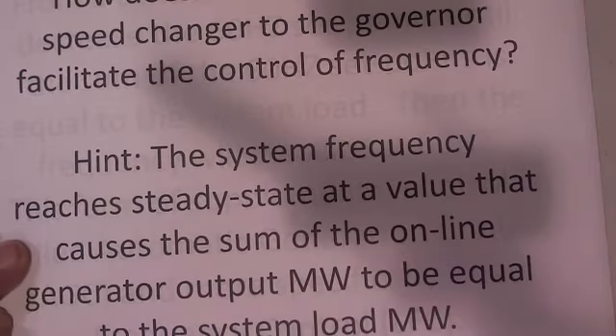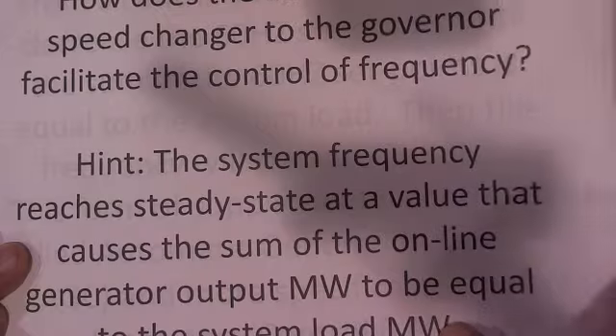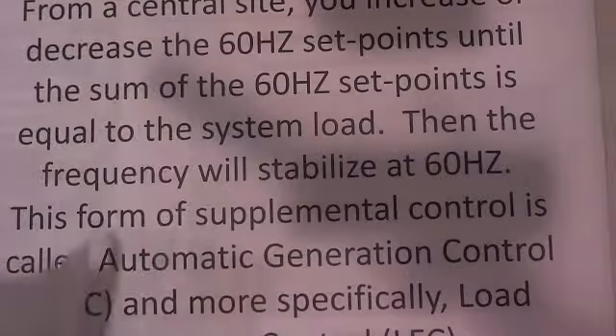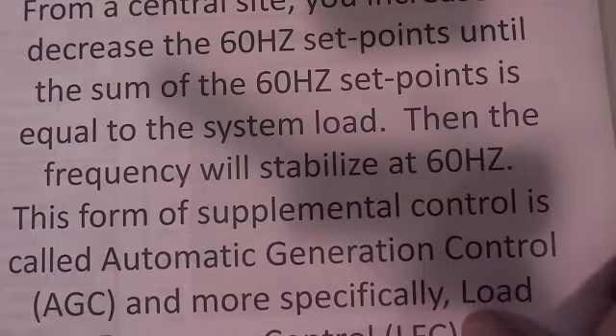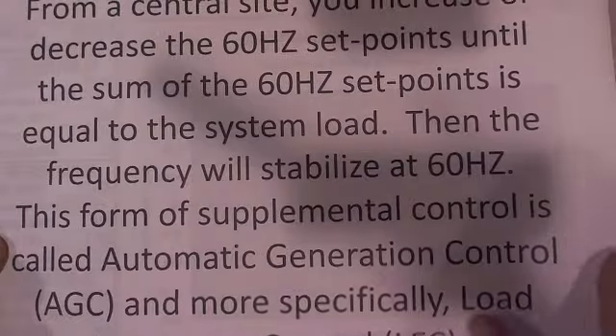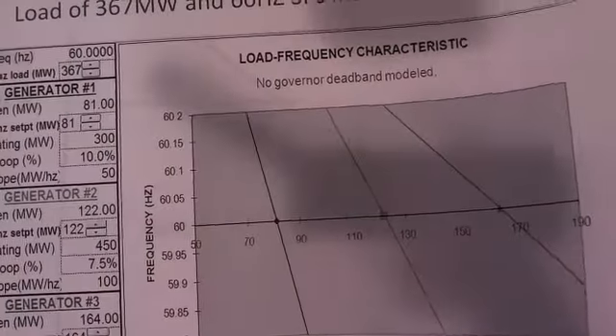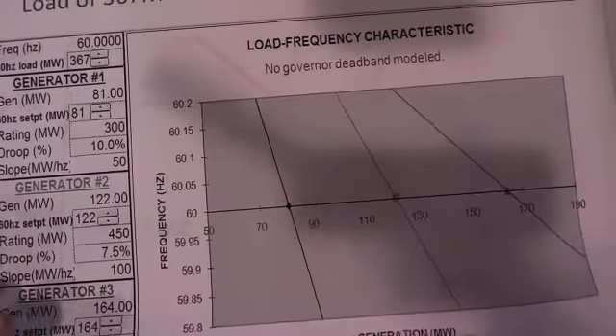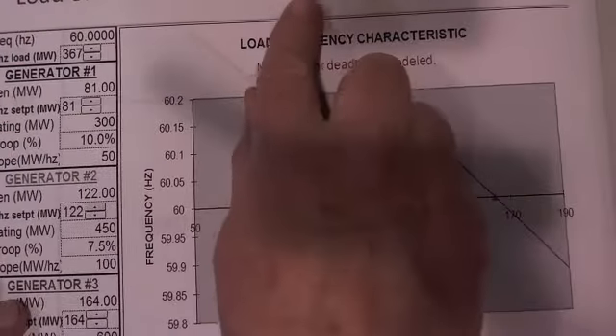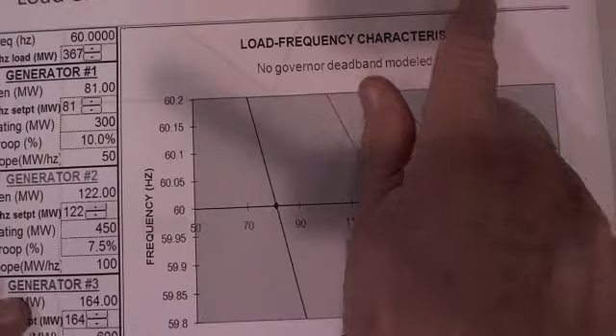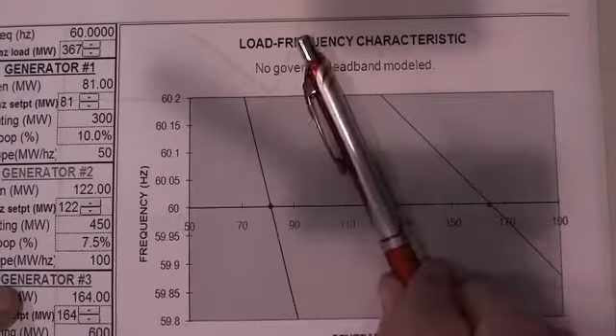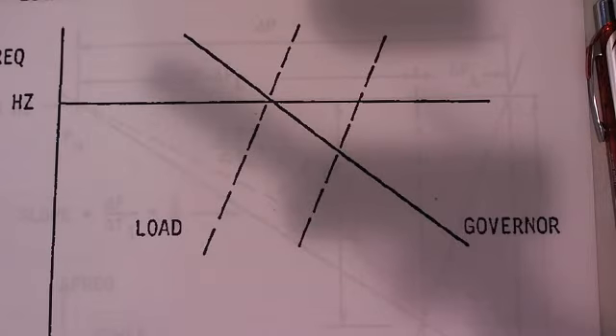The frequency reaches a steady state at a value that causes the sum of the online generator output to be equal to the system load. That goes without saying here. So if a load is 367, then the speed changers must increase by 7, and we talked about that. They actually move over. You can't see it here with that little bit.